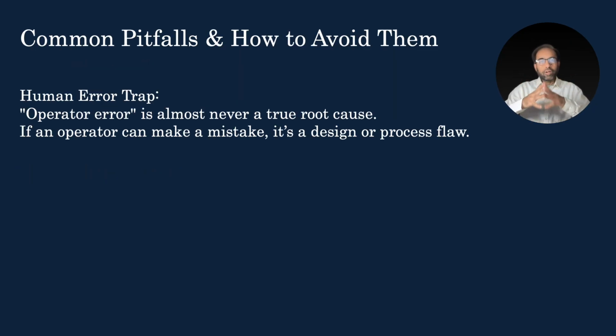In my years of leading product development, engineering, operations, quality, and regulatory, I have seen some incredibly smart people make the exact same mistakes during root cause analysis. Let's make sure you don't. Pitfall number one, operator error. Operator error is almost never a true root cause. If an operator made a mistake, it's usually because the procedure was ambiguous, the training was inadequate, or the work instruction ergonomics were poorly designed. Ask why the operator made the mistake. Ask yourself these questions.